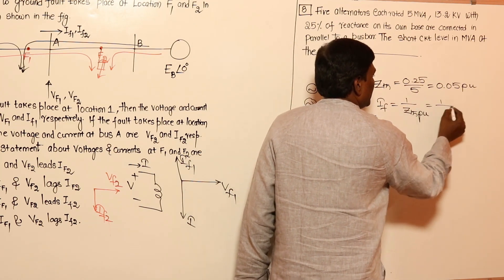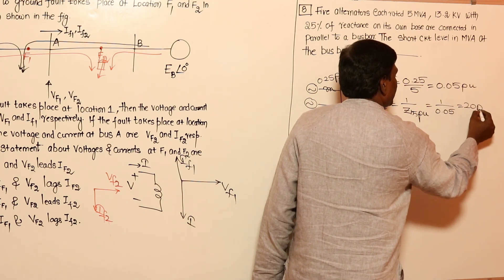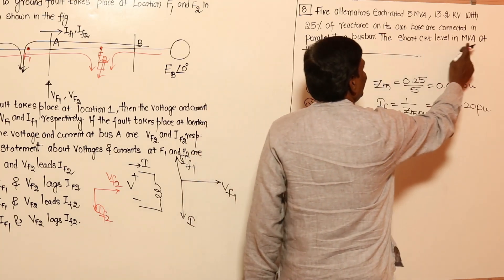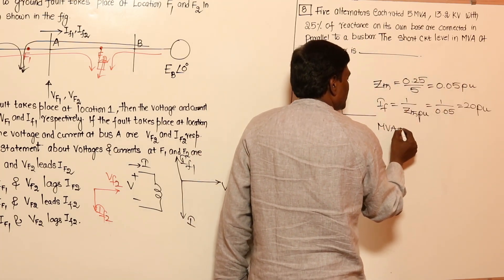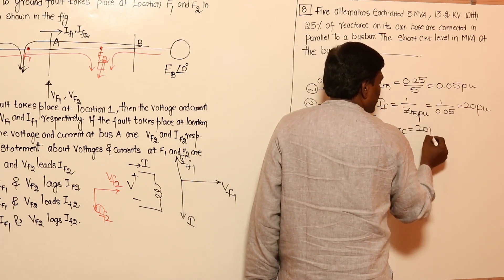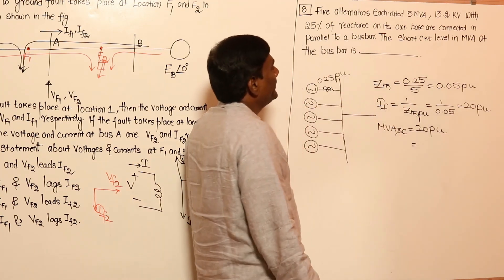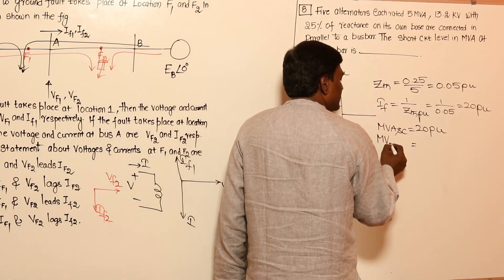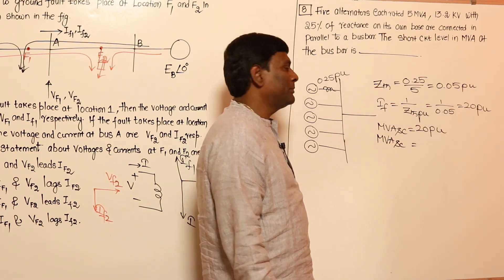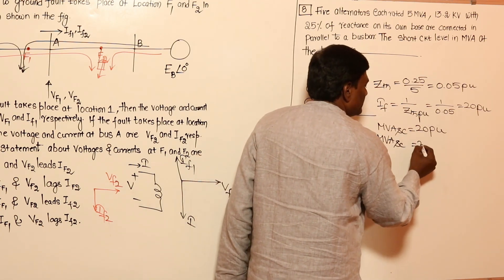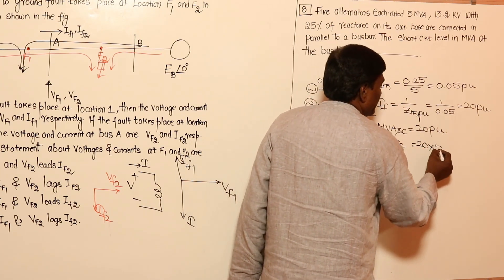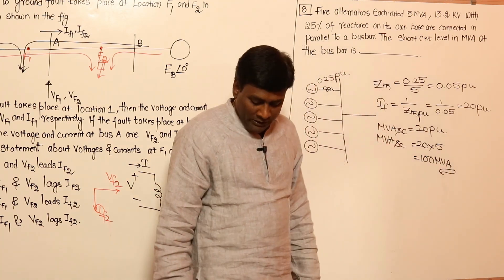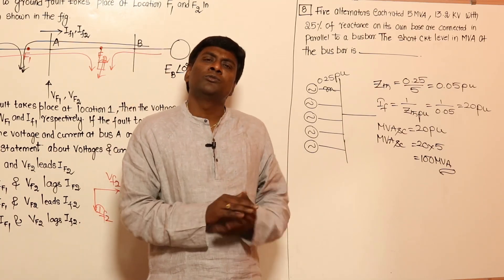Z-Thevenin equals 0.05 per unit. Fault current level equals 1 divided by Z-Thevenin, so fault current is 1 by 0.05 equals 20 per unit. The short circuit MVA is also 20 per unit. In actual MVA, multiply per unit by base: 20 into 5 MVA base equals 100 MVA. That's a simple problem — don't get scared in fault analysis; small questions only come.